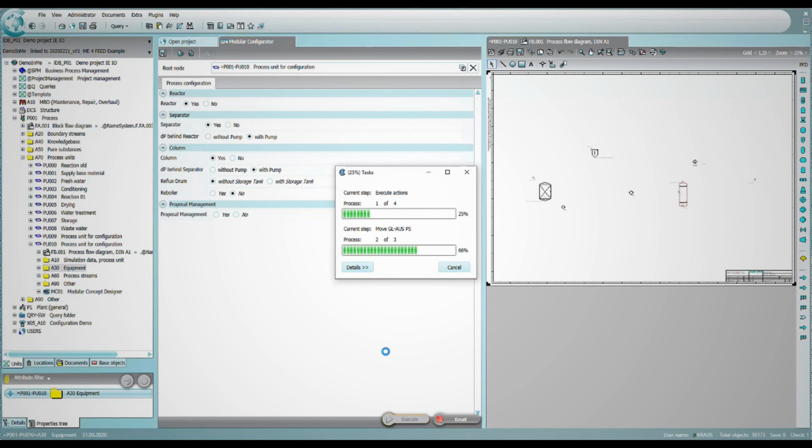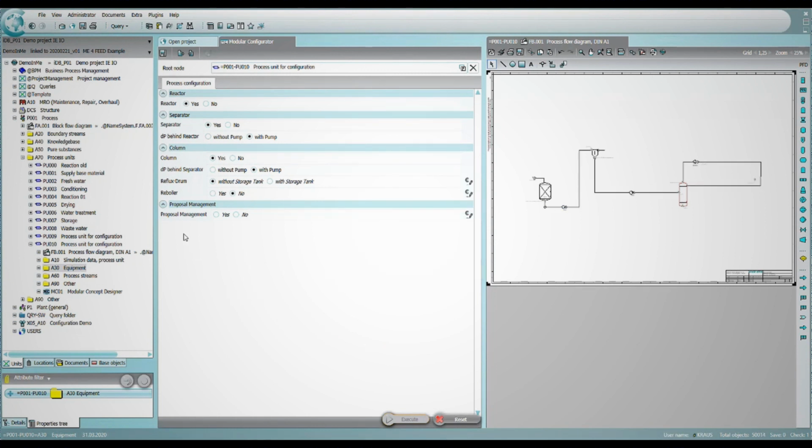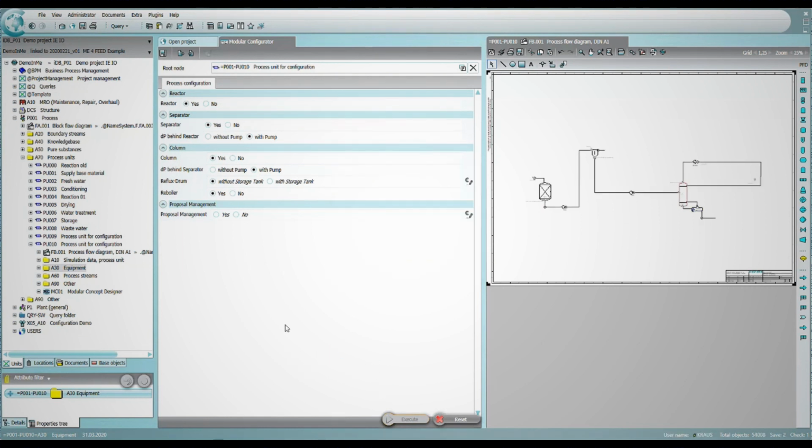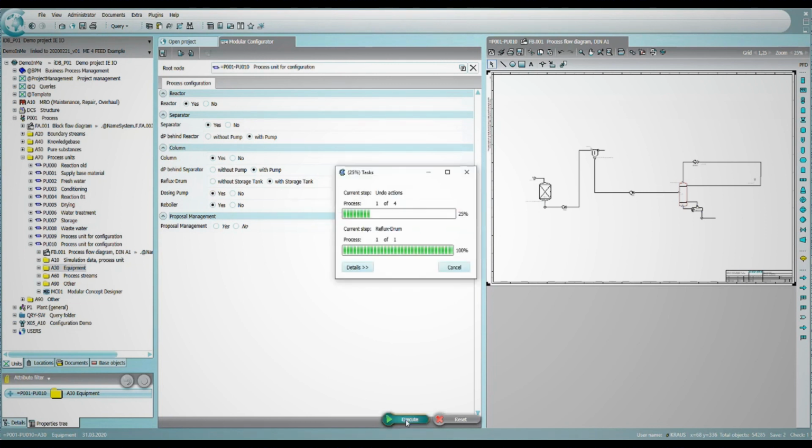COMOS cross-discipline design templates allow for capturing and merging design templates covering all involved disciplines, like process, piping, mechanical, I&C, amongst others, thus providing a true multi-discipline project configurator. Options can trigger sub-options, which means that, for example, a new instrument function on a P&ID can bring its own sub-templates for detailing out the corresponding loop schematics, or a motor brings its own wiring schematic and MCC bucket. Items come with pre-filled data sets and data sheets, which again may vary based on certain project configurations.